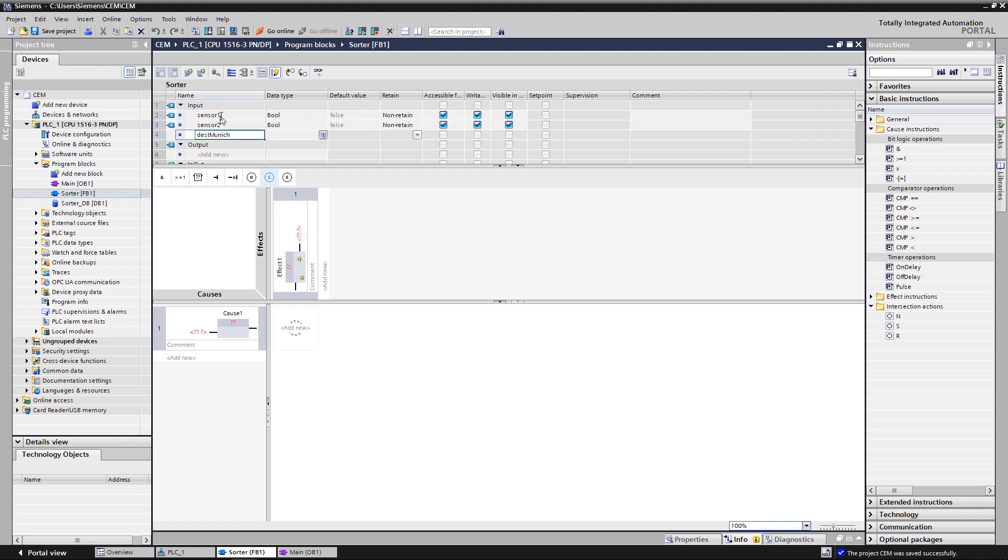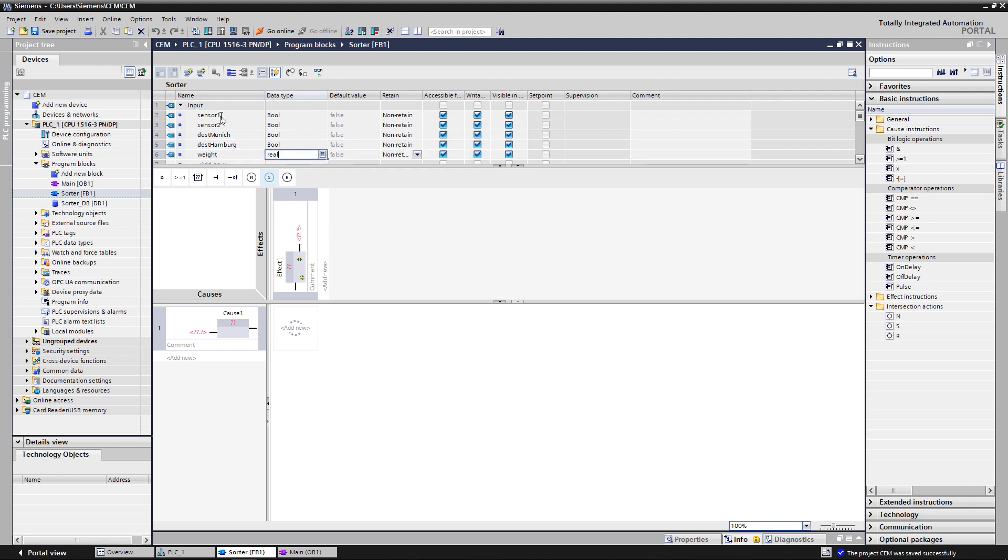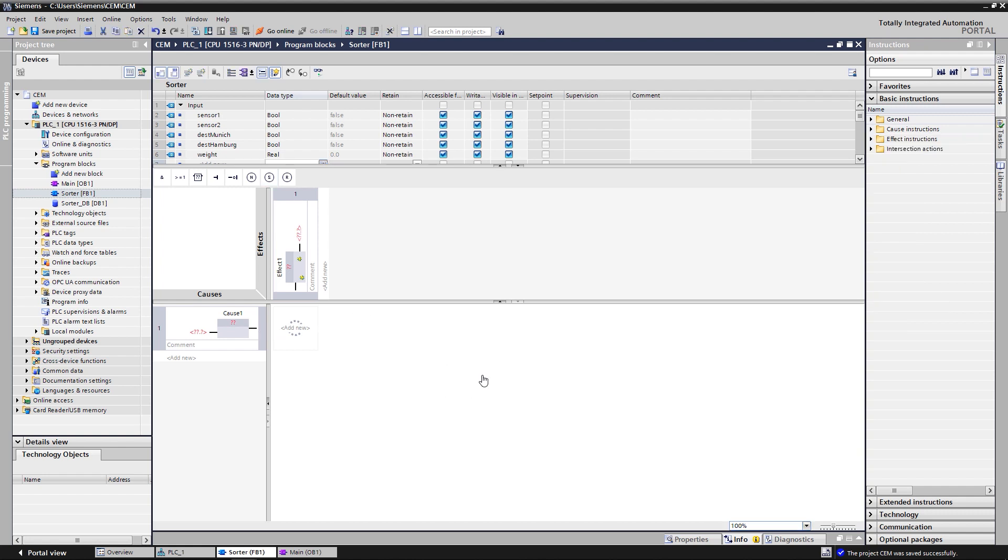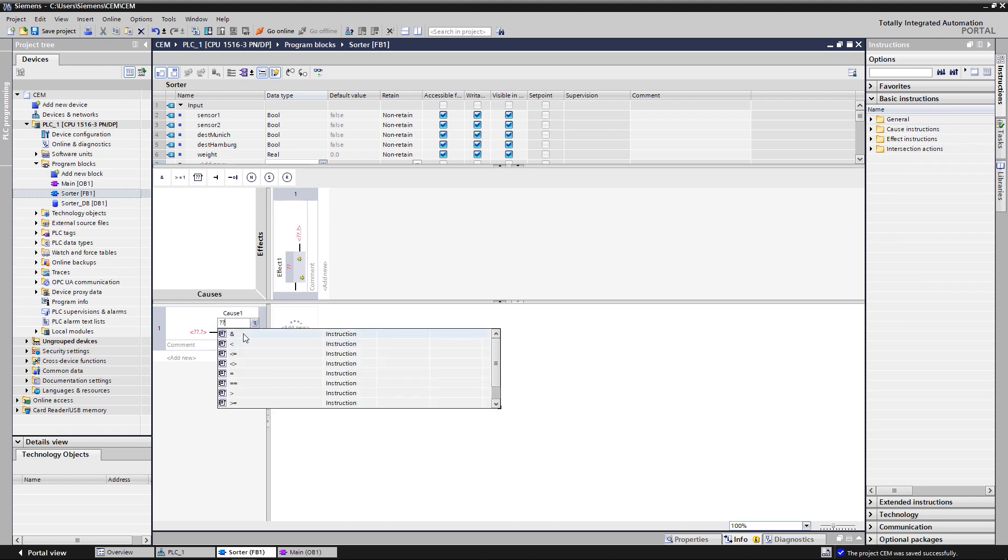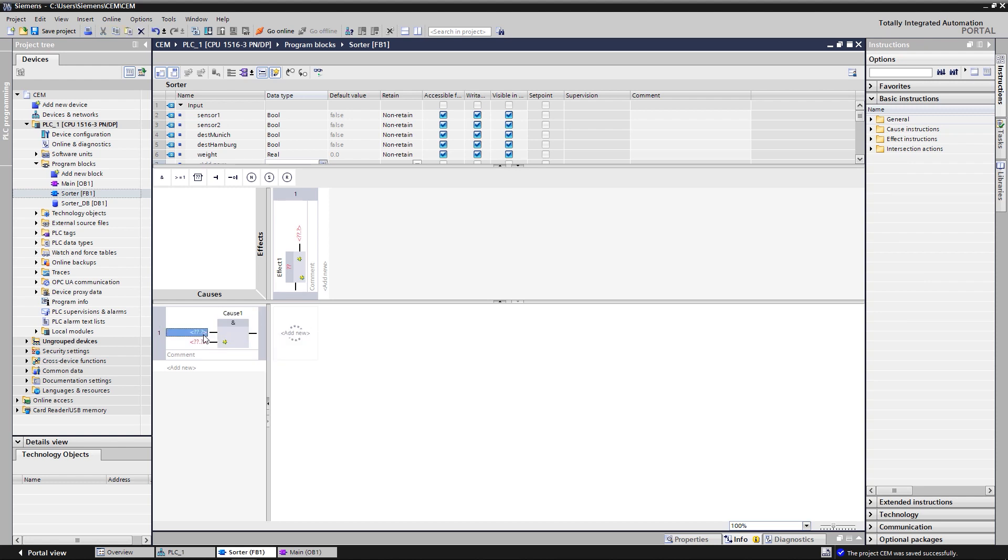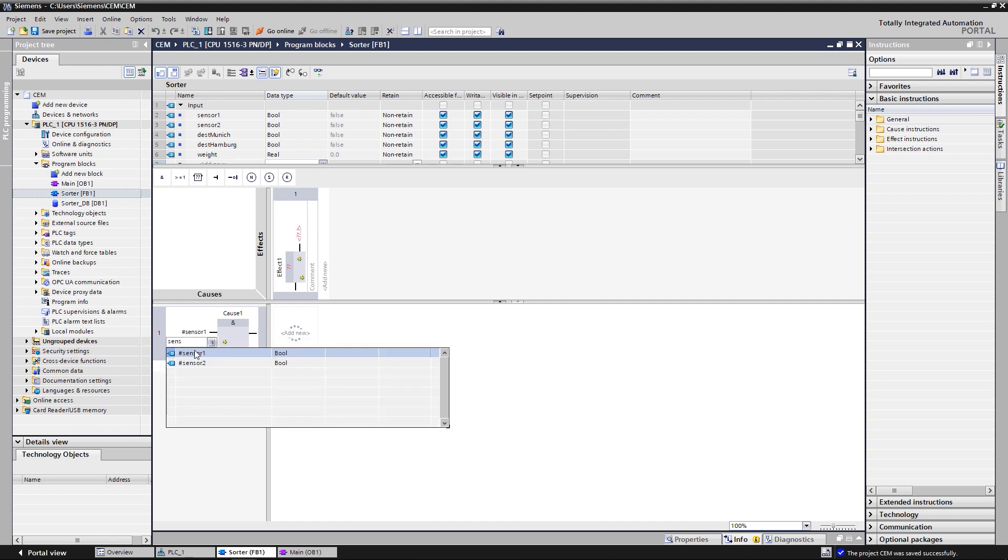For the example program, four causes are required, which query whether the preconditions for the baggage transport have been met. At first, let's create the cause with the logic operation AND, which checks whether a bag has been placed on the belt. This is detected by two light barriers that the bag must pass. The cause is named Get Sensors.